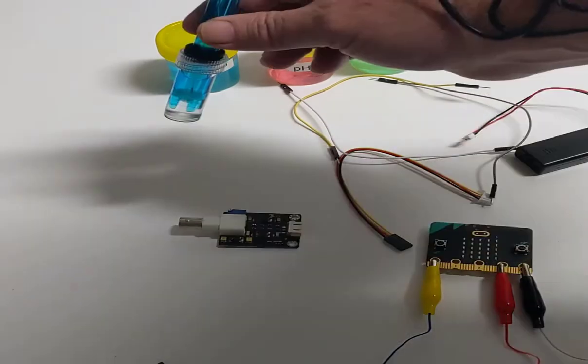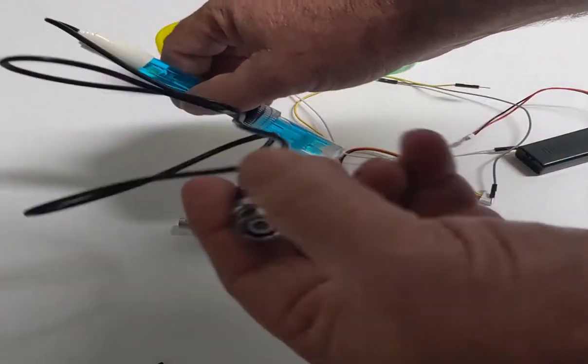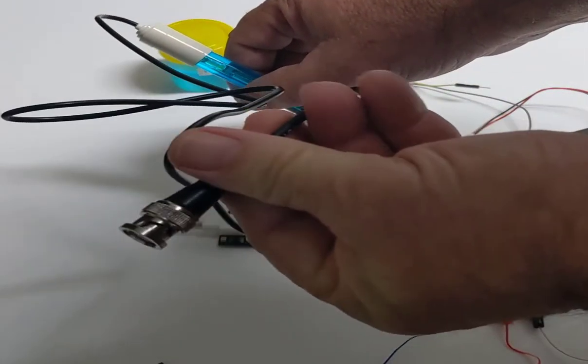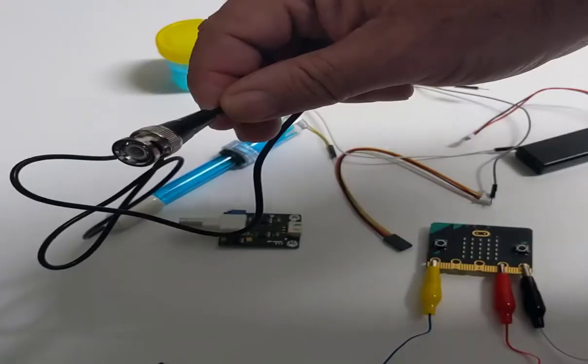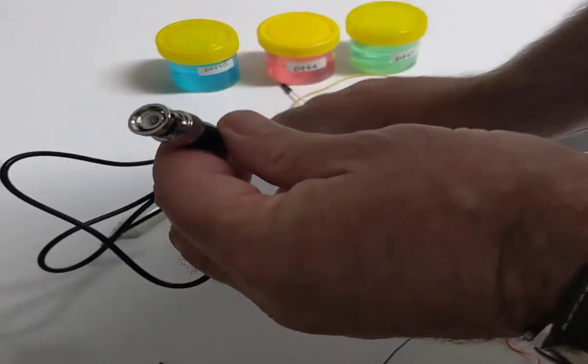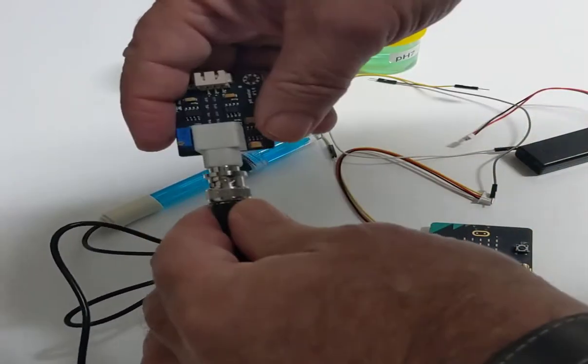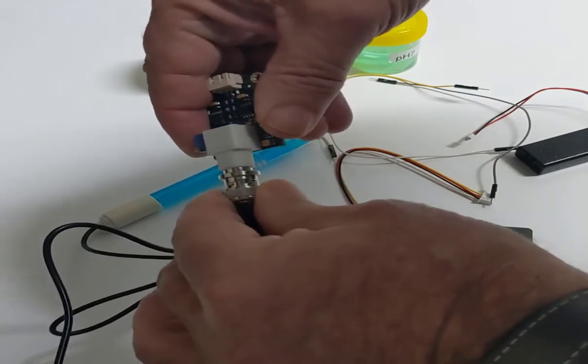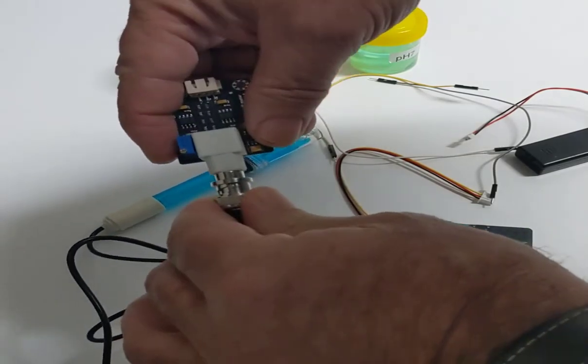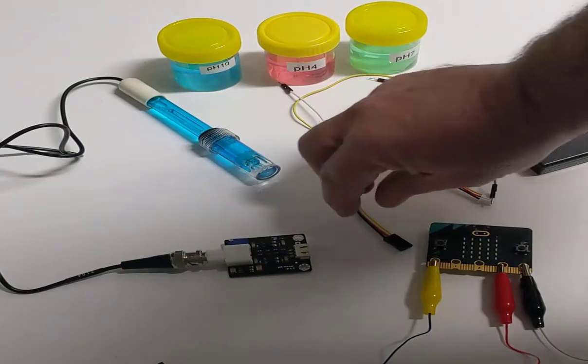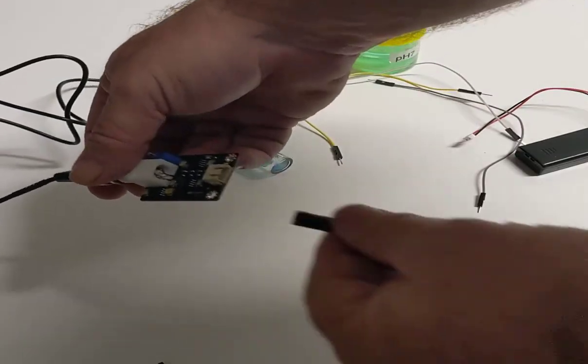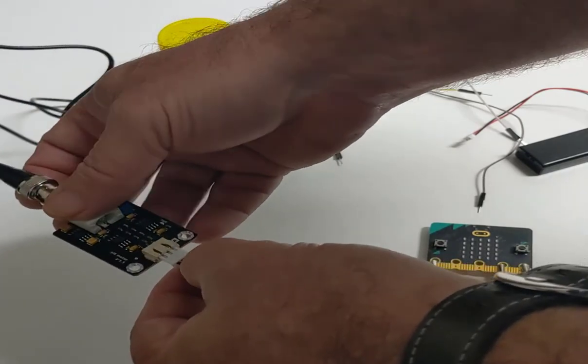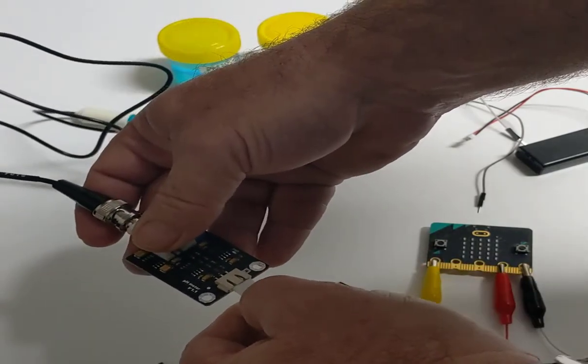Now, the pH electrode probe, notice the other end of it is one of these connectors. It's called a BNC connector, and it plugs in by twisting and locking. So simple, place it in, twist and lock. Then the other end of the sensor signal converter is connected via this wire, which came with it. It only goes in one way.